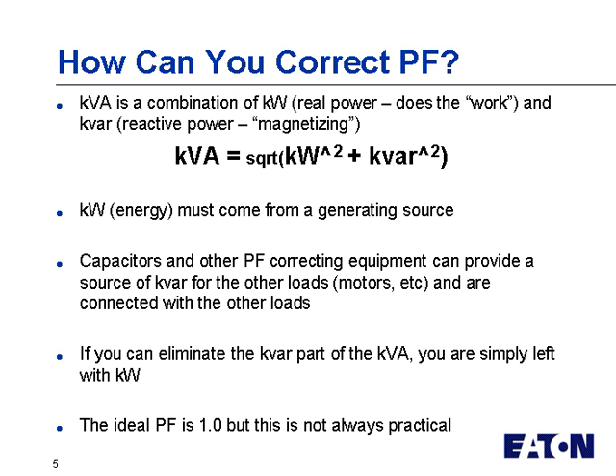kVA is a combination of real power, or the power that we say does the work. It moves the equipment, it provides heat, things like that, and reactive power, or kVAR. And kVAR, we typically say, is the magnetizing power. So it's the power that magnetizes the motor that allows it to spin. It's power that magnetizes the transformer that allows it to operate.